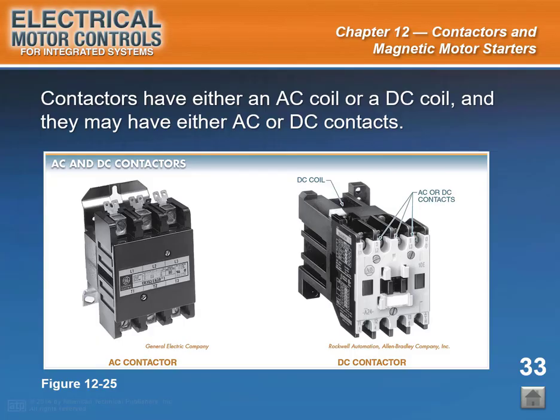Slide caption: contactors have either an AC coil or a DC coil, and they may have either AC or DC contacts. See Figure 12-25. AC contactor assemblies may have several sets of contacts. DC contactor assemblies typically have only one set of contacts. In three-phase AC contactors, all three power lines must be broken. This creates the need for several sets of contacts.